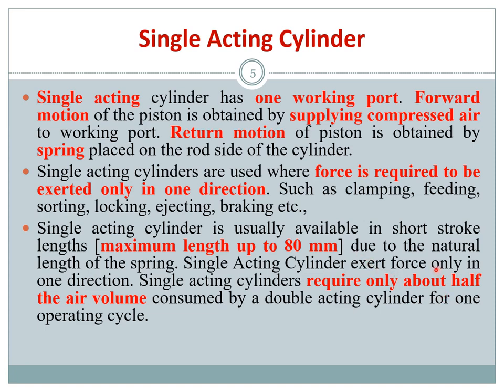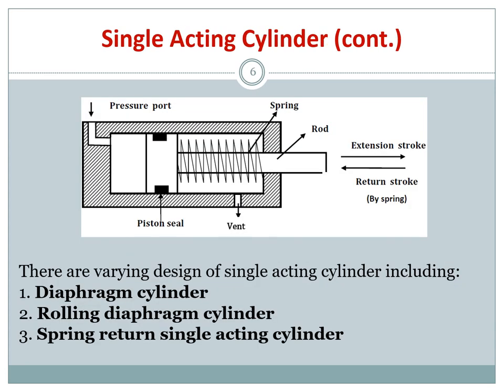Single acting cylinders exert force only in one direction and require only about half of the air volume consumed by a double acting cylinder for one operating cycle. This is because a double acting cylinder has two ports — one to extend and one to retract — so it requires twice the air volume.